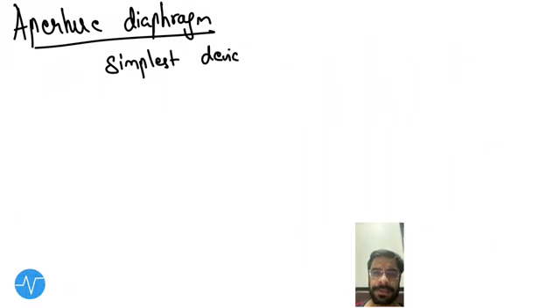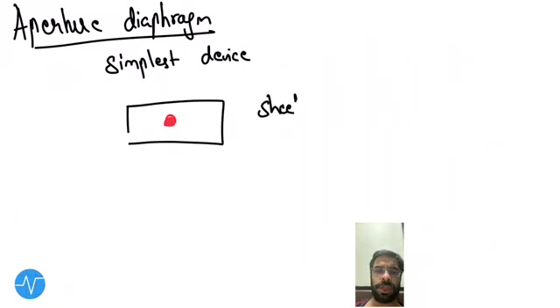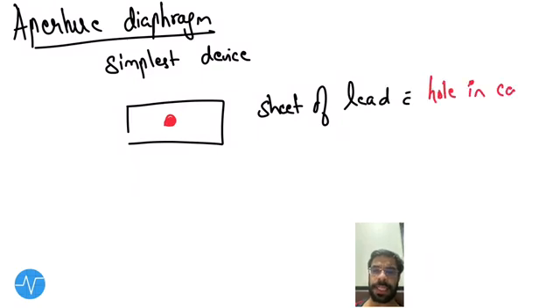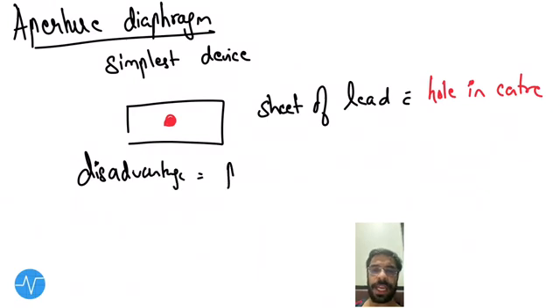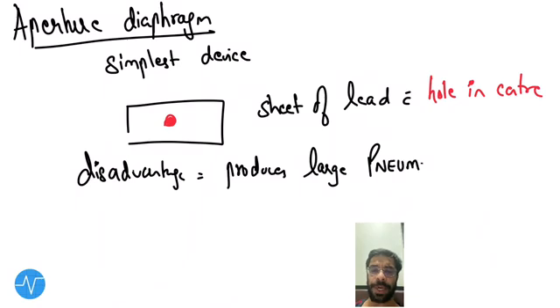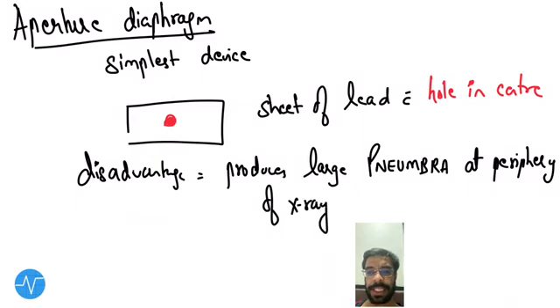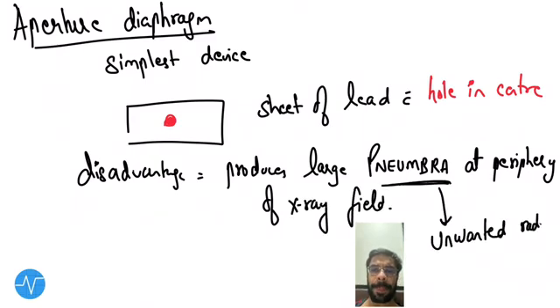The first restricting device is the aperture diaphragm — it is the simplest device. In the diagram, the red spot represents the gap, which is the hole in a sheet of lead. The disadvantage of the aperture diaphragm is that it produces a large penumbra at the periphery of the x-ray field. Penumbra is unwanted radiation at the periphery.